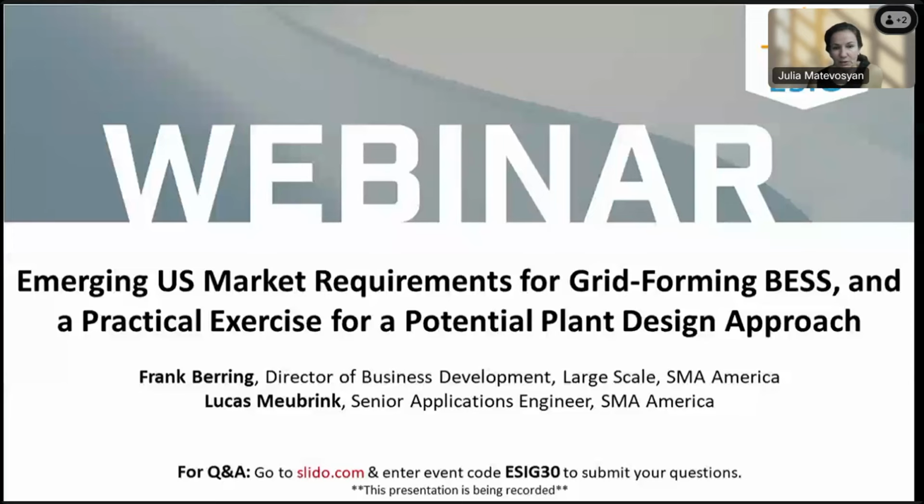All right, so to introduce today's topic, as you probably all know, renewable generation is dominating the interconnection queues, and legacy synchronous generation is scheduled to be decommissioned in the coming years. These are exciting trends, but they also introduce new challenges to maintain grid stability and enable additional new renewable generation to come online. Grid-forming battery energy storage systems have become a well-recognized contributor towards grid stability, and several system operators have announced plans to implement grid-forming requirements in recent months. In this webinar, two subject matter experts from SMA will share recent market news pertaining to grid-forming battery energy storage adoption and functional test requirements.